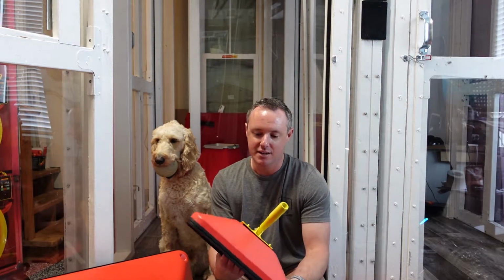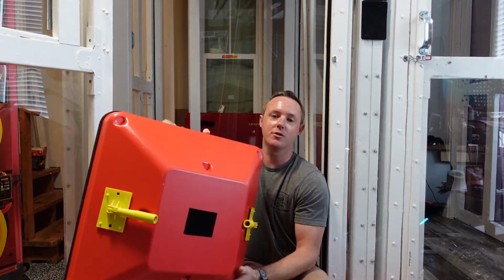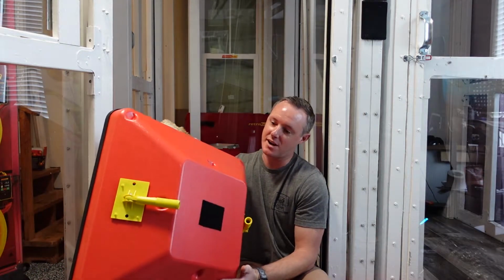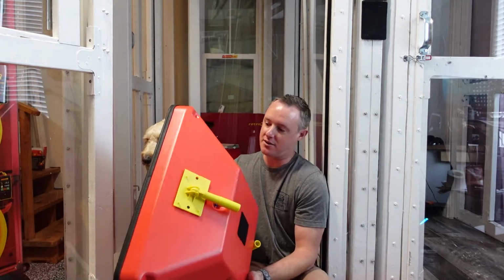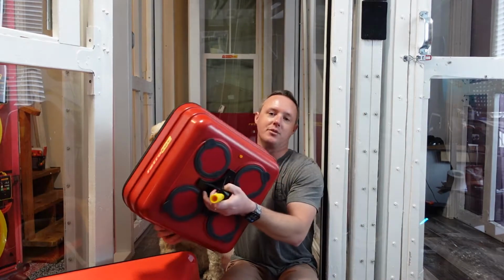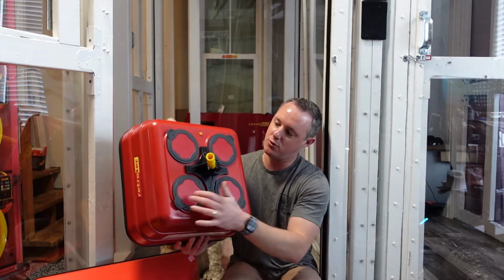Here at Retrotec, we make a few different pressure pans that you can use. This is our smallest one, which is great for looking for leaks around can lights, supply registers, over some bath fans, receptacles, switch boxes, smaller penetrations like that. And we also have our larger 24 by 24 inch pressure pan, which is great for looking for leaks around some room returns, larger bath vents, and things like that.